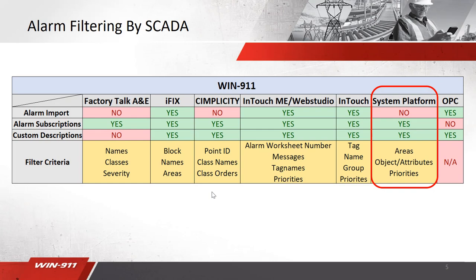This is a rundown of all the SCADAs that WIN911 supports for our direct connect method. As you can see, we'll be focusing on System Platform today. To bring your alarms over in System Platform, you'll need to use the alarm subscription method. In doing so, you will be able to filter your alarms based on area, object attributes, and priorities.